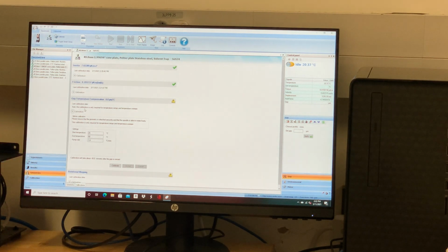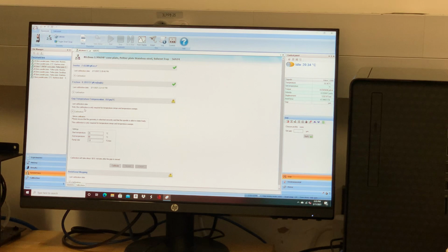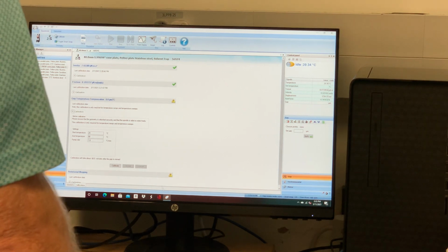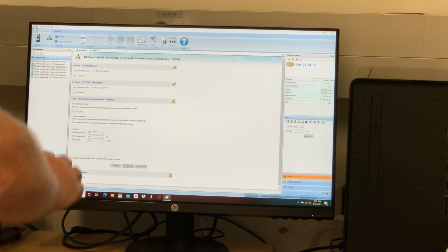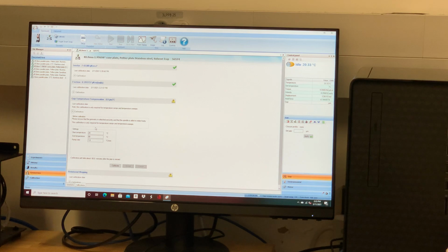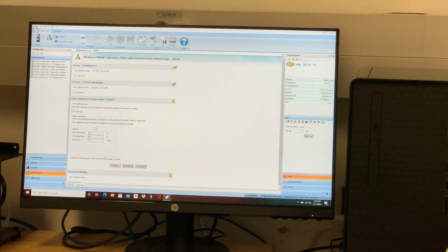You only need to run this calibration if you're doing temperature ramps. If you're just doing isothermal runs, you would just go to that temperature and zero the gap. You don't have to worry about thermal expansion. I assume the people that are going to be using the oven will probably be doing temperature ramps. It's very easy to do. It just takes a long time. All you do is put your start temperature in. This calibration only needs to be done once, because the factor for heat expansion isn't going to change for the geometry. And you would put the range of all the procedures you're going to run, whatever you think your range is going to be for everything you're going to run.